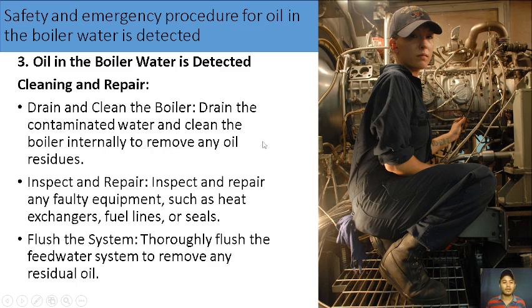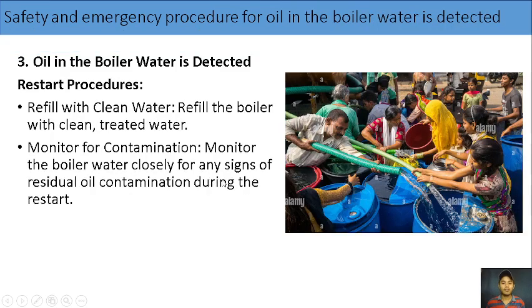After the immediate action, we have to clean and repair. Drain the contaminated water and clean the boiler internally to remove any oil residues. Inspect and repair any faulty equipment such as the heat exchanger, fuel lines, or seals. And thoroughly flush the feed water system to remove any residual oil. After that, we can now restart. Refill the boiler with clean, treated water, and monitor the boiler water closely for any signs of residual oil contamination during the restart.